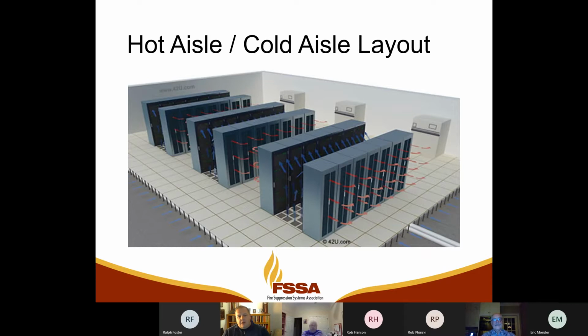I want to talk about this phrase hot aisle, cold aisle, and then hot aisle, cold aisle containment, or just aisle containment. It's the idea that on a rack, hopefully you can see my cursor here, there's a cool face of the server where cold air goes in, and then it picks up heat as it blows across the server, and then on the backside, that's the hot side of the rack. Well, when we arrange the cold sides facing each other, we make a cold aisleway. We can walk down this aisle, and that's the two cold faces facing together. Naturally, if we keep doing that in repeating fashion, we're going to have the hot aisles facing each other.